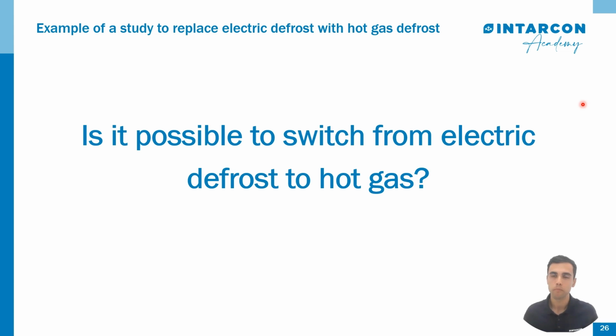And the question is: is it possible to switch from electric defrost to hot gas? It depends. Hot gas defrost is possible in systems where the evaporators are small or the heat demand for defrost is low, as in the system illustrated above. In addition, it is crucial to manage the number of evaporators defrosting simultaneously in order not to exceed the capacity of the system. In the example with R134, the conversion could be carried out, although it is recommended to study each case.